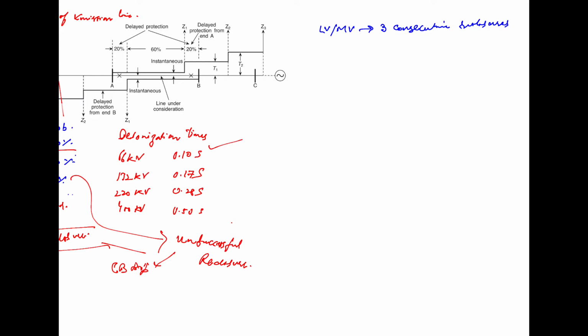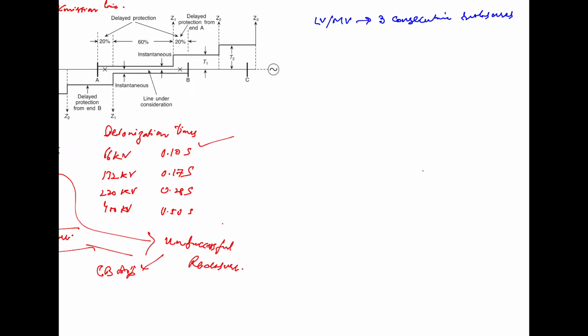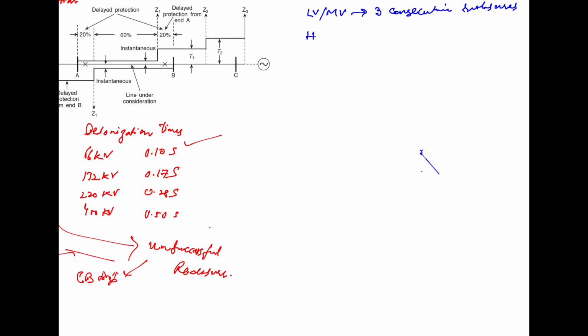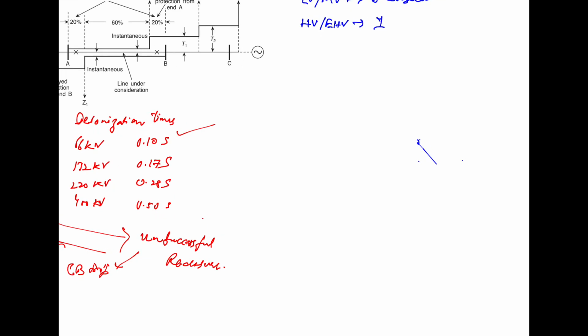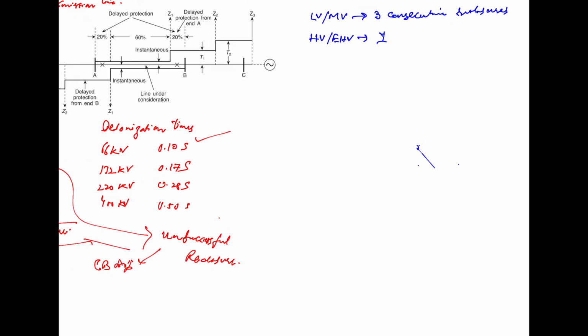The multiple reclosers in the low voltage and medium voltage systems help in burning out the object responsible for the fault, say a tree or branch, thus helping in clearing the fault. Only one recloser is allowed in the high voltage and extra high voltage systems, and if done sufficiently fast, it helps in improving the stability of the system.